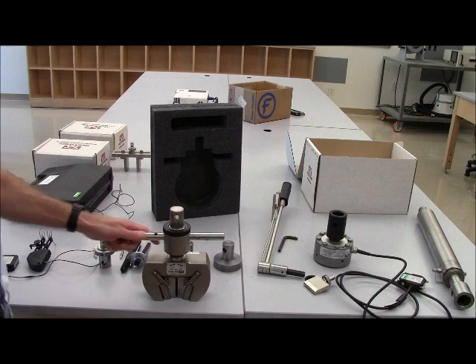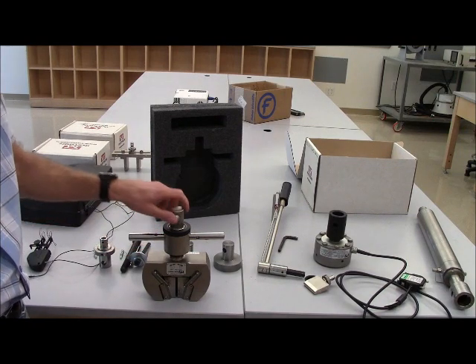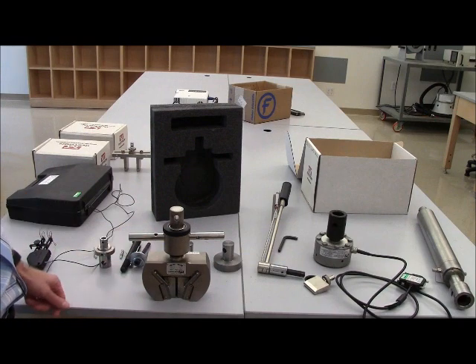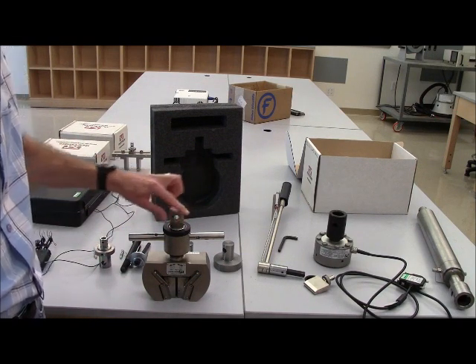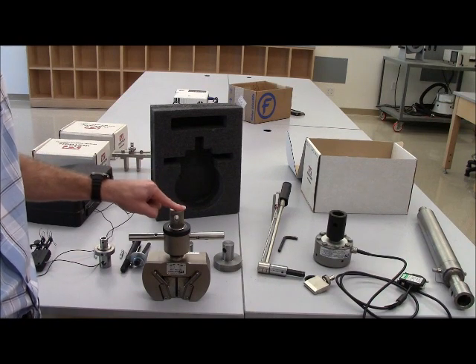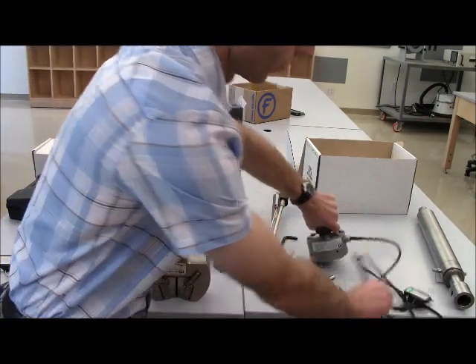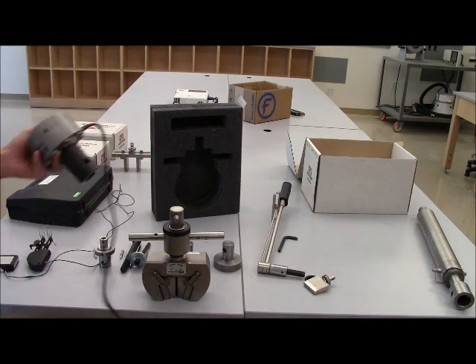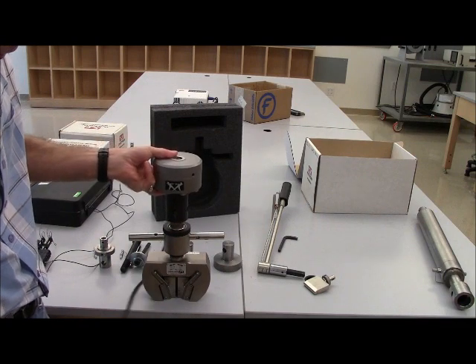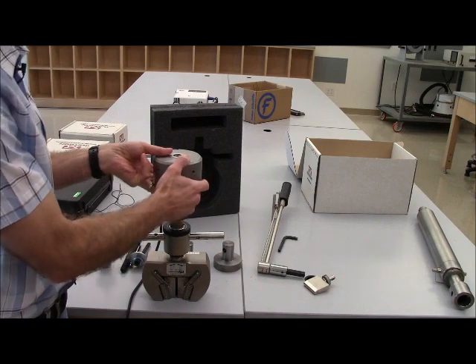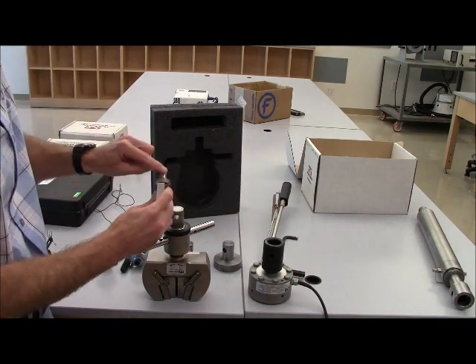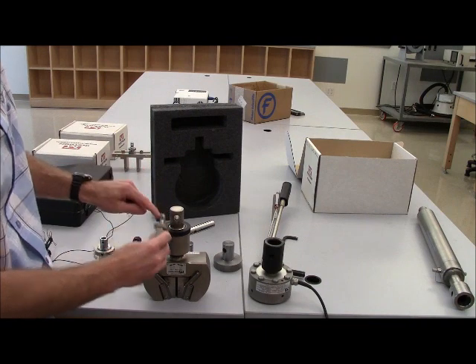While I have the wedge action grip out, I want to talk about the fact that Instron has two different interfaces between attachments and load cells. One is a large interface and one is a smaller interface. The large interface is referred to as a type DM interface, and that's Instron's labeling. So for example, the wedge grips that we have and the 50,000 newton load cell have a type DM interface, and so these fit together, and there is a half inch pin that goes through to connect them.